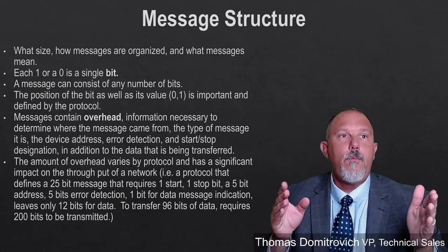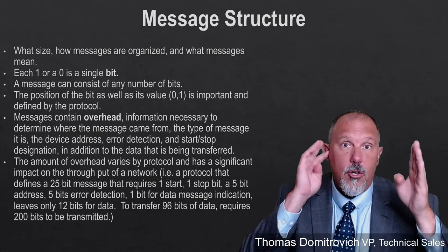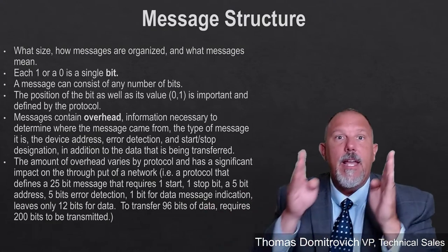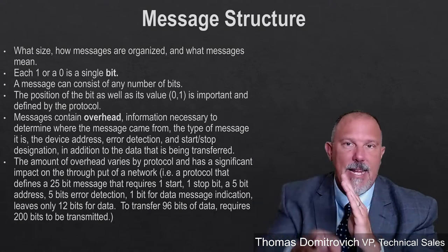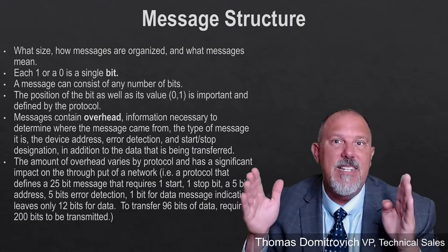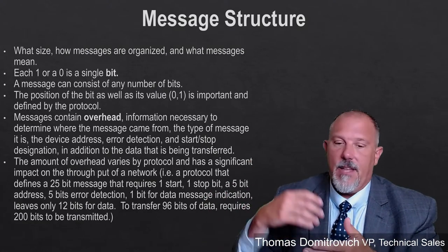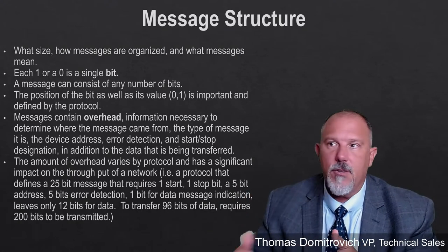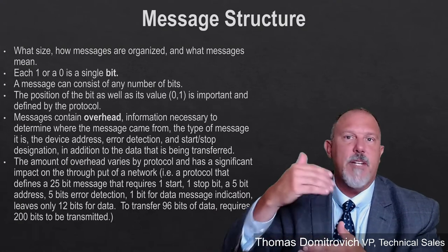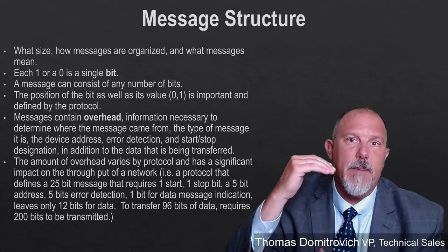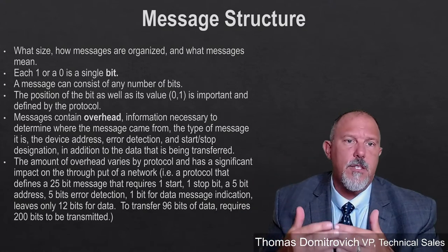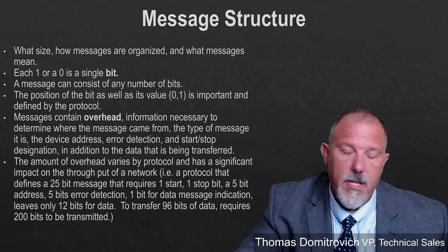So you can look at all the ones and zeros and say, am I asking the right message? Am I getting clobbered? I'm sending out 11000010101, but I'm getting something different in my monitoring. So it could be I've got a corrupt file. It could be that my data lines, my grounding and bonding isn't done correctly. My shielding isn't done correctly. I may not have put my terminating resistor in, and I'm getting clobbered due to a reflective wave, all these different things. So being able to see the message is really critical when you're troubleshooting.